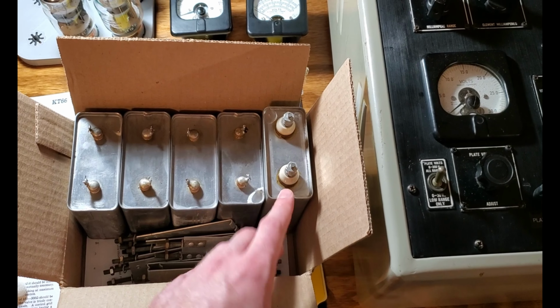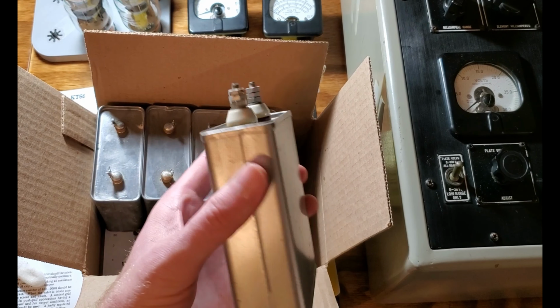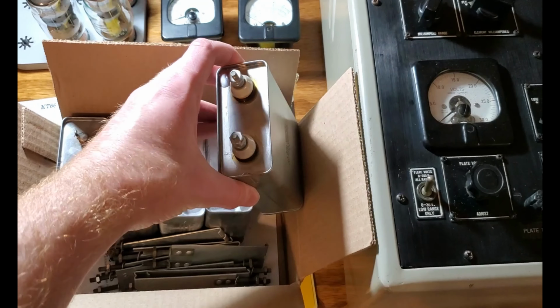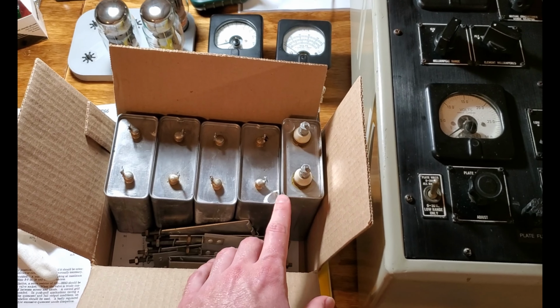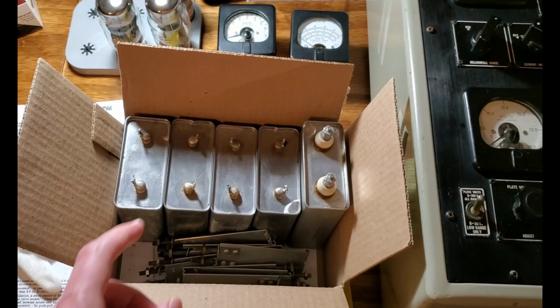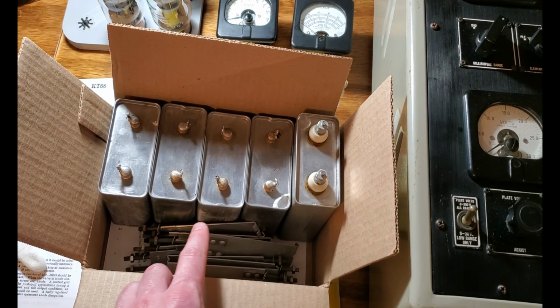I don't remember what the B stands for, but it's a biohazardous chemical. And you can see this capacitor, this one's okay. This is a more recent replacement. You can tell it doesn't match the other ones, which were those Astrons. The reason being is one of the capacitors clearly had failed. Where this was positioned in the power supply, back in the unit down in here, there's a big stain where clearly the residue from that PCB oil leaked out of one of these capacitors. And so I tested these with some decently high voltage as well as just an LCR meter. If I just squeezed the can by a little bit, the capacitance would change by over 100% on all of these. So these are all really bad, not good.